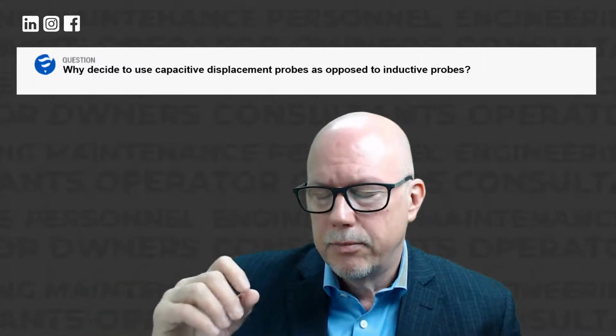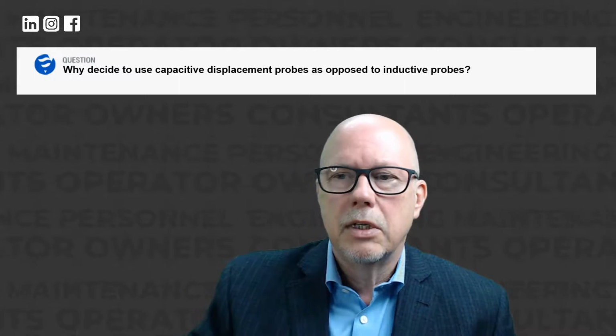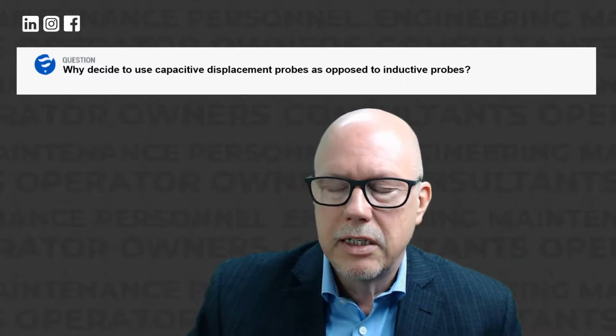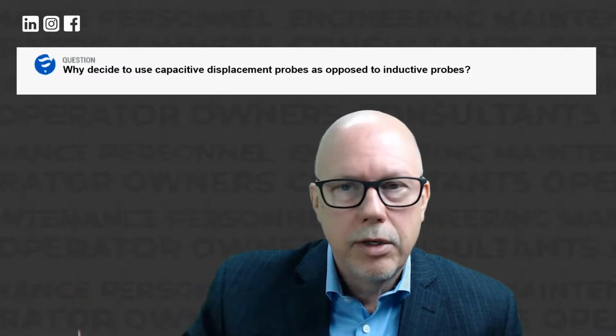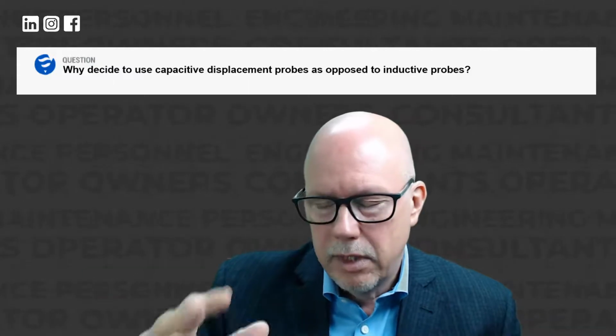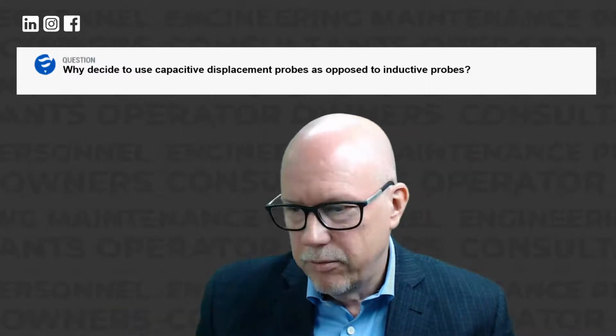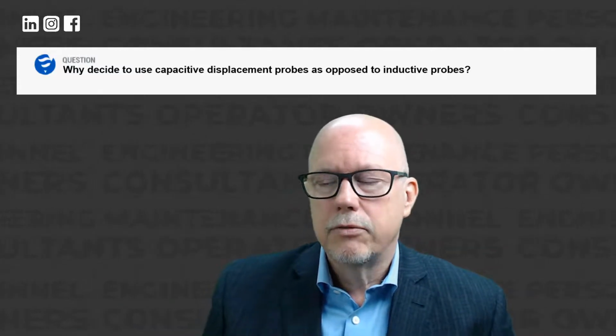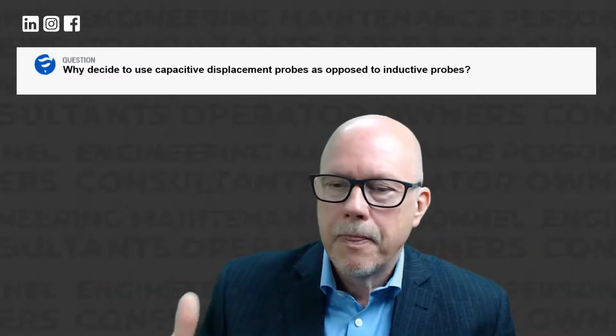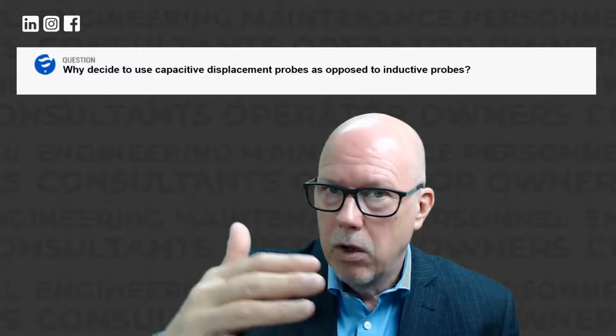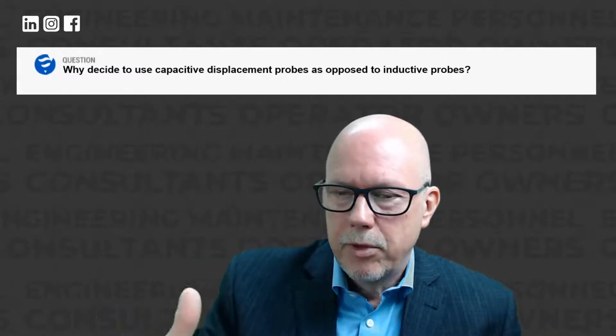The reaction, the performance will be exactly the same. So you don't need to wonder how your sensor is going to measure if it's facing brass or steel or different types of steel, iron, manganese, zinc, whatever material your shaft is made of. You'll have the exact same performance. Whereas inductive probes, depending on the type of material, you'll have a very different response from your sensor. So each individual sensor has to be calibrated for its location. So if you have 8 sensors, you have to calibrate all 8 of them, and you have to calibrate for their location and the material that will be facing the sensor. That has to be done.